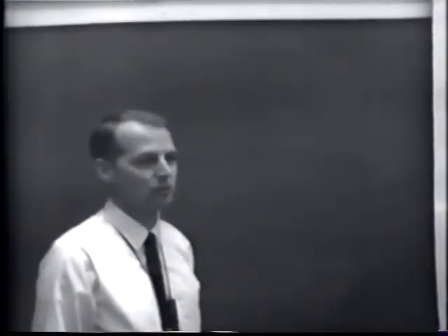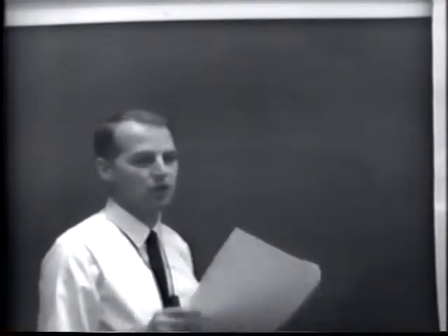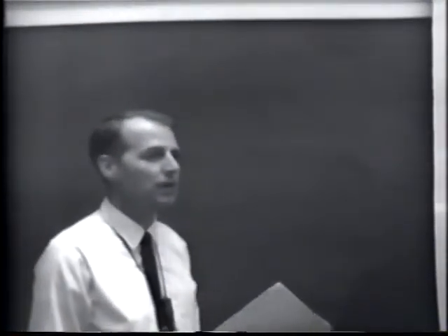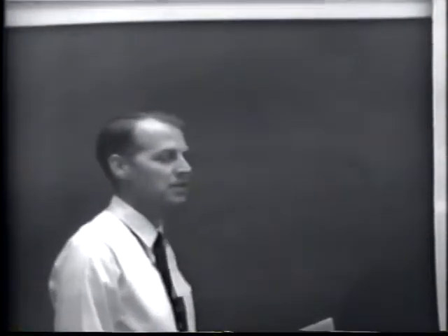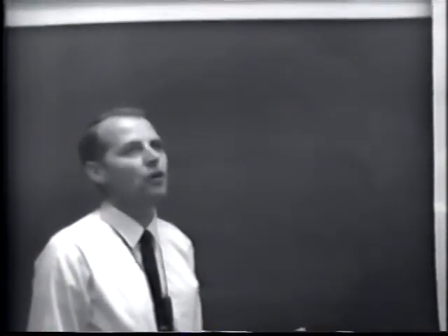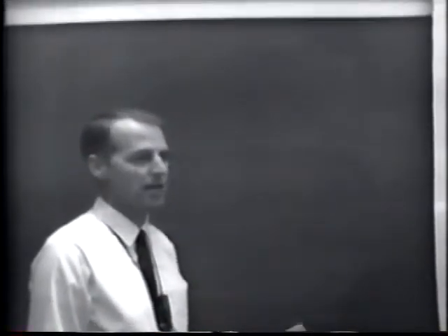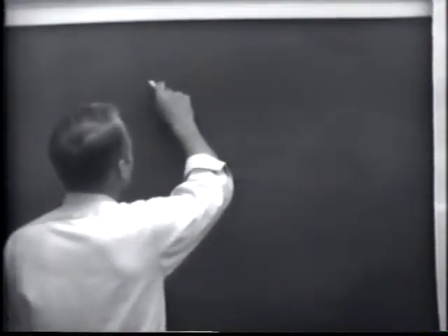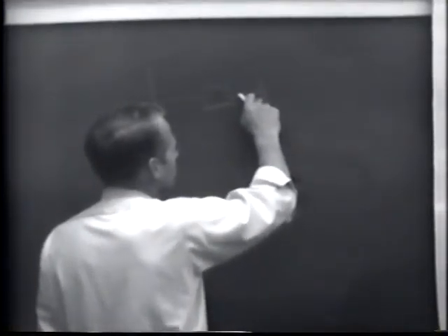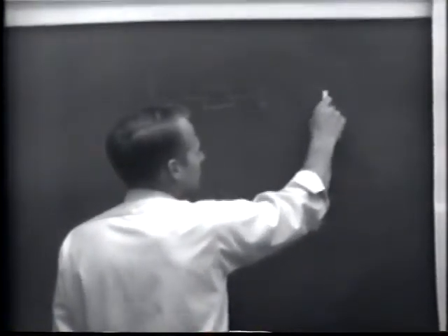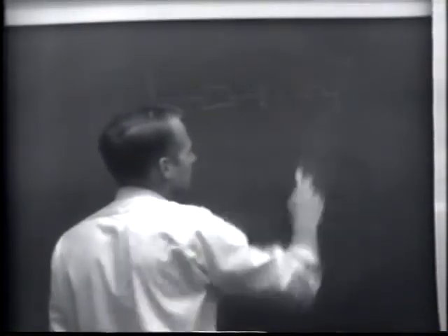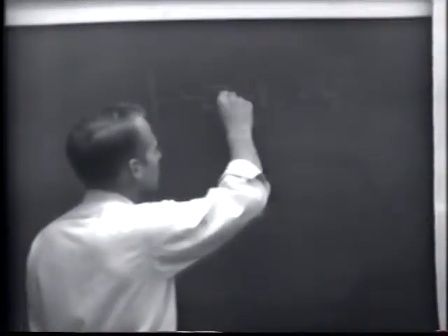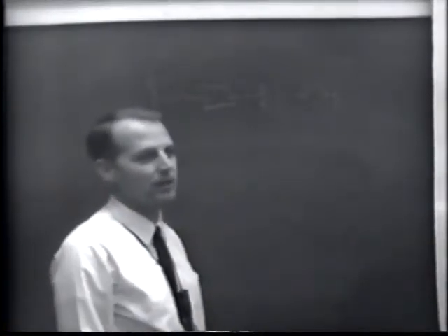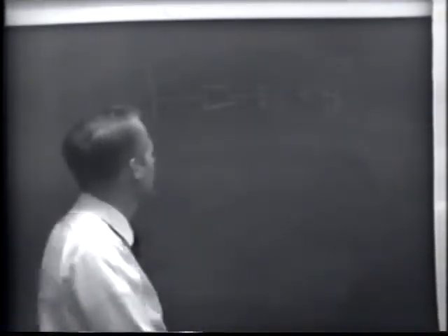To help maintain these circuit breakers, we always put a disconnect switch on either side of the 69 kV circuit breaker, a 161 kV circuit breaker, or a 345 kV circuit breaker, or some type of isolating means on both sides. In some cases where we have a bus with a circuit breaker connected and then a transformer immediately connected to that breaker, we sometimes omit a disconnect switch here and rely on the secondary circuit breaker of the transformer. Because when you have any one of these breakers open for maintenance, the transformer is completely dead anyway.